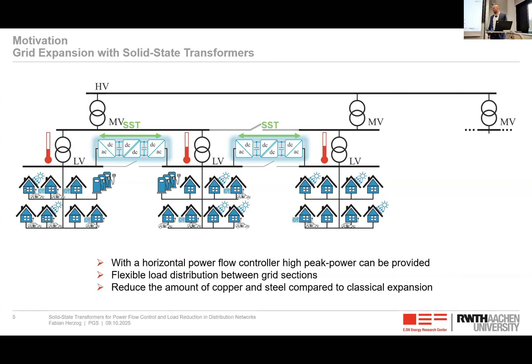So what exactly is a solid state transformer? Here in the top right, we can see a classical transformer. It's a very large component. The solid state transformer basically adds power electronics to this transformer. With this, we are not bound to 50 Hertz frequency anymore. And the higher the frequency in a magnetic component, the smaller the magnetic component gets. So we use higher frequencies like 1 to 10 kilohertz, and then we can shrink the transformer and have a much smaller component here. So this is what we use inside the solid state transformer.